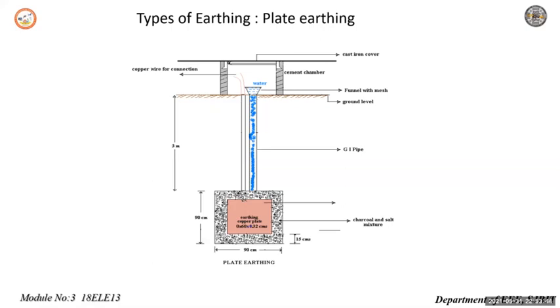The earth connection is provided with the help of a copper plate or galvanized iron plate. The copper plate size is 60 centimeter by 60 centimeter by 3.18 mm, while the GI plate size is not less than 60 centimeter by 60 centimeter by 6.3 mm. GI plates are commonly used nowadays. The plate is embedded 3 meters into the ground, kept with its face vertical. The plate is surrounded by alternate layers of coke and salt, with a minimum thickness of about 15 centimeter. The earth wire is drawn through a GI pipe and is perfectly bolted to the earth plate. The nuts and bolts must be of copper for a copper plate and of galvanized iron for a GI plate.